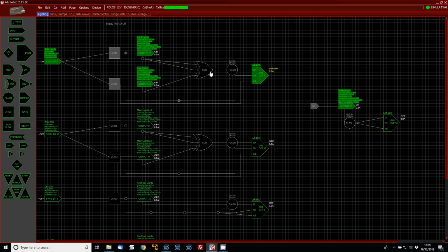Then the flash statement here, this is an XOR. On the bottom of the outputs we've got a fault pin. It goes into an XOR, and then it flashes in the event that there is a fault. You can actually toggle the fault on here, and you'll see that flashing on here, which would then cause the green LED on the Grayhill panel to flash to indicate there is a fault with these outputs.